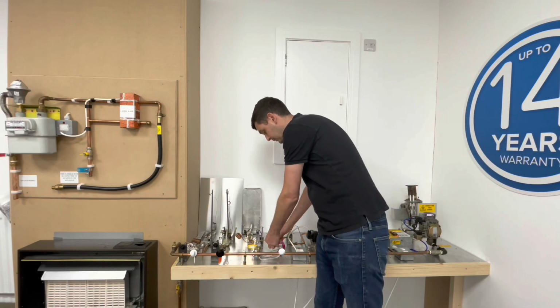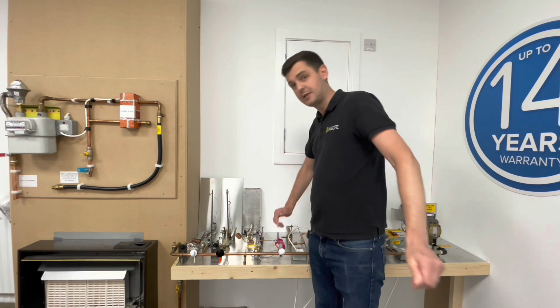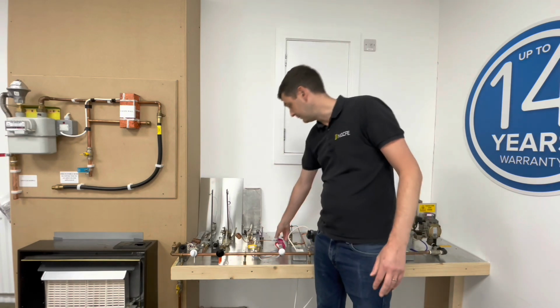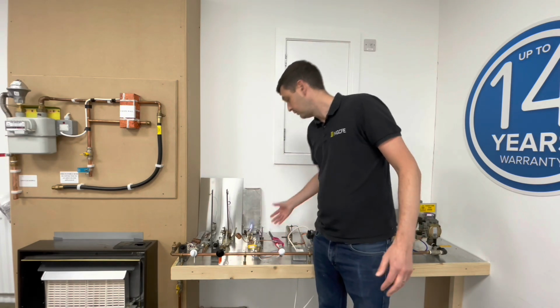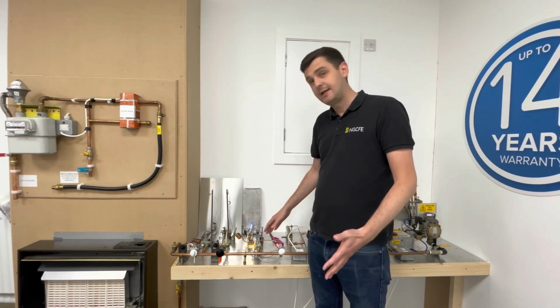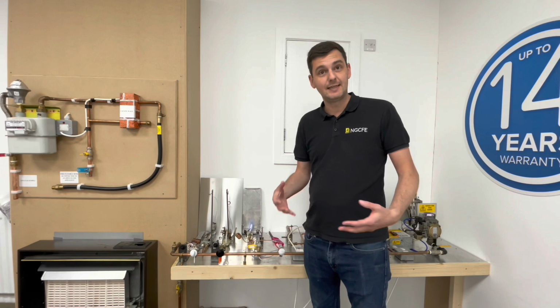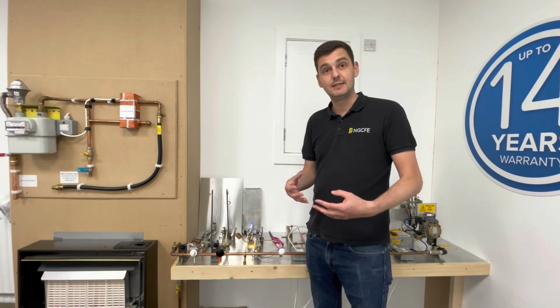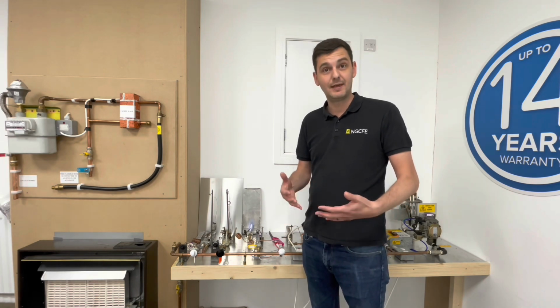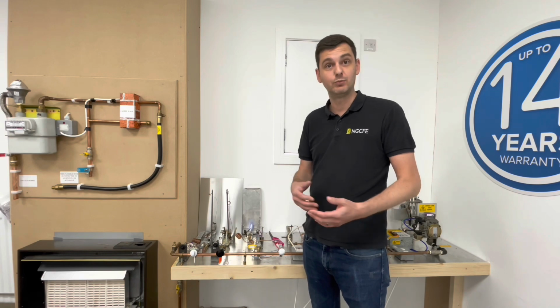Because the thermocouple is still hot, if I press that in now, I've made the magnet again, and we can hear we've got gas again at the burner. So all that's happening here is we've introduced a break in the system, but that break is controlled via some form of thermostat or some form of device that is breakable.